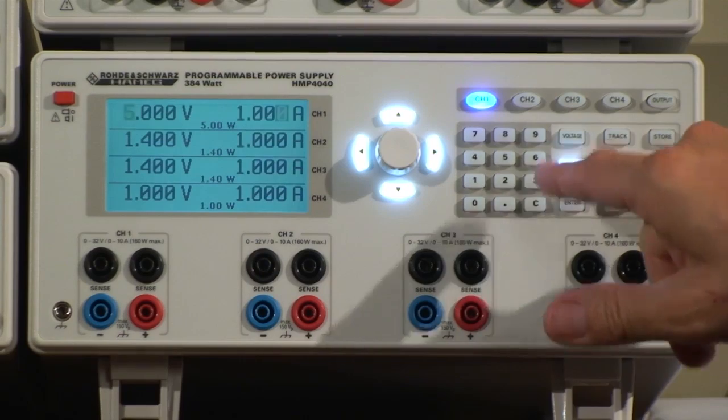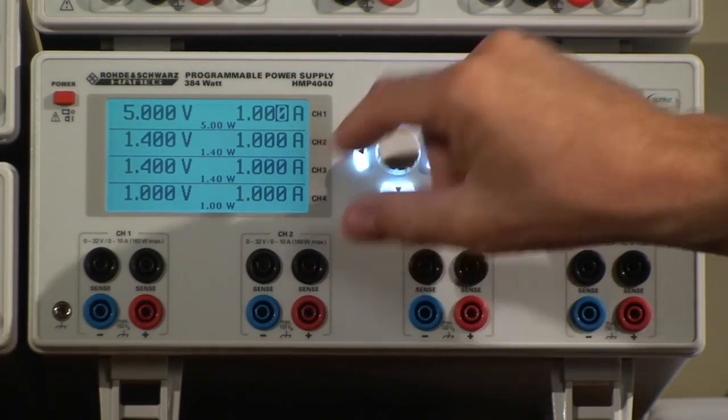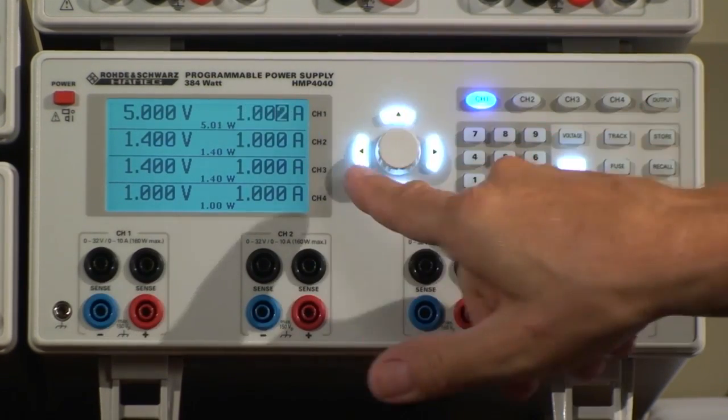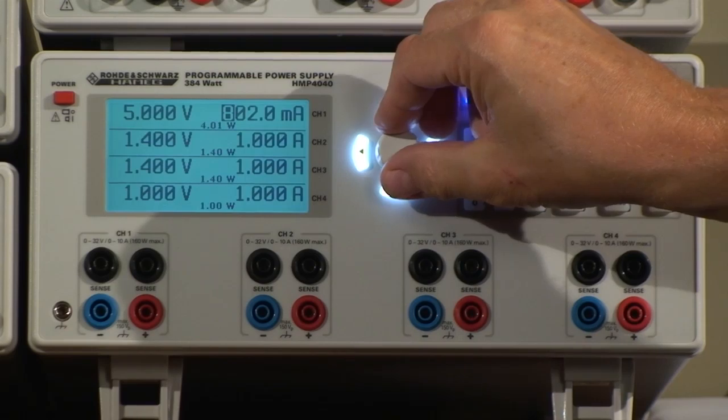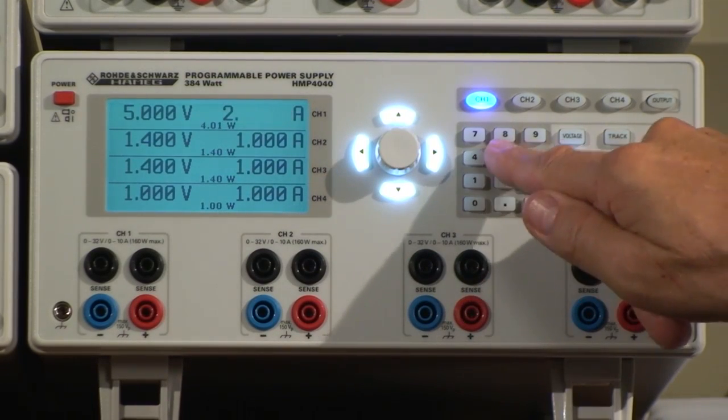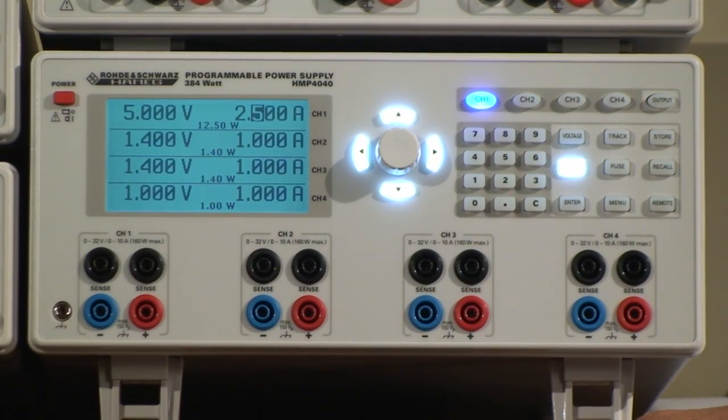I can do the same with the current on the same channel. I can change it by turning the knob here, use the cursor, or I can say 2.5 amps. That goes for the rest of the channels, of course.